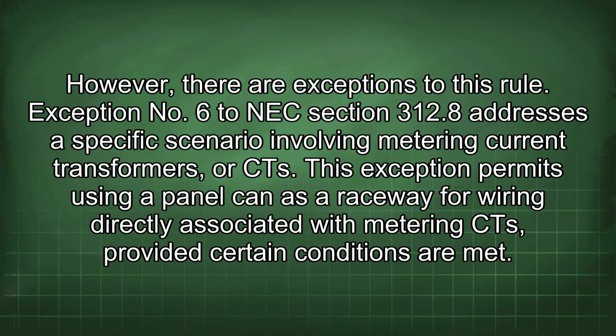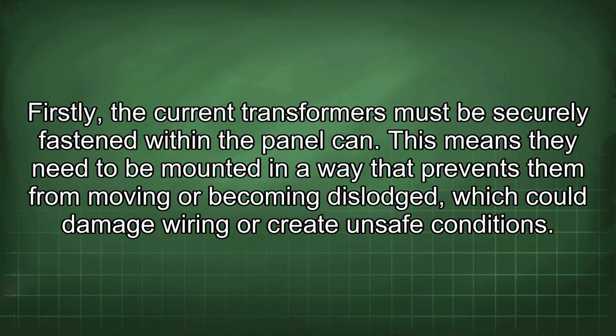Exception No. 6 to NEC Section 312.8 addresses a specific scenario involving metering current transformers, or CTs. This exception permits using a panel can as a raceway for wiring directly associated with metering CT, provided certain conditions are met. Firstly, the current transformers must be securely fastened within the panel can. This means they need to be mounted in a way that prevents them from moving or becoming dislodged, which could damage wiring or create unsafe conditions.